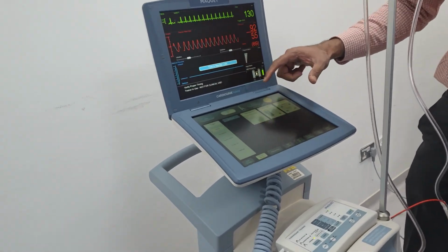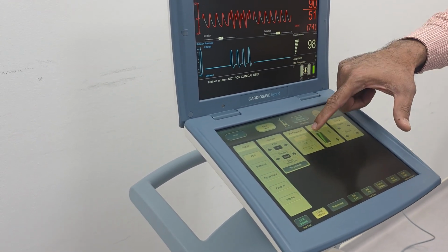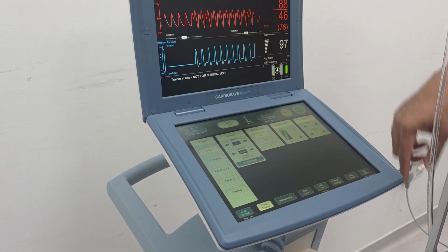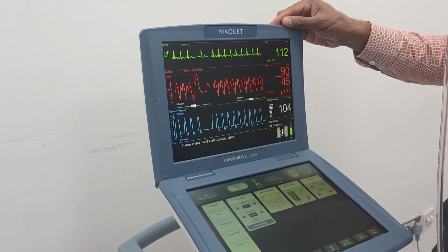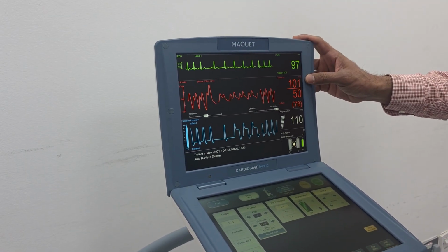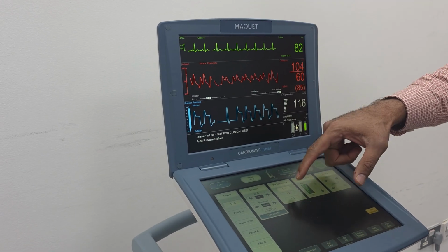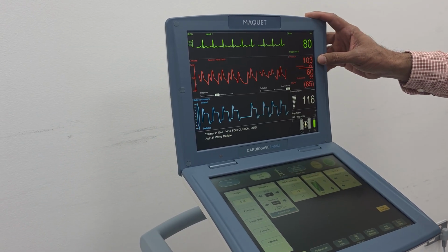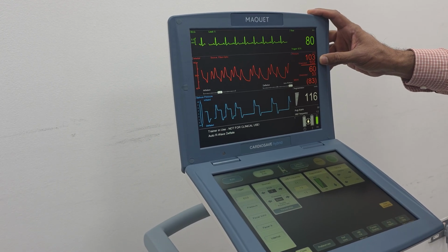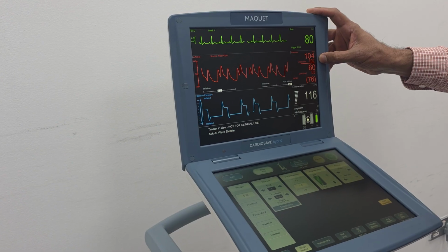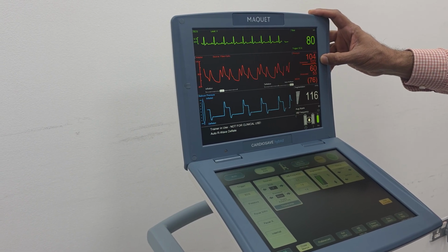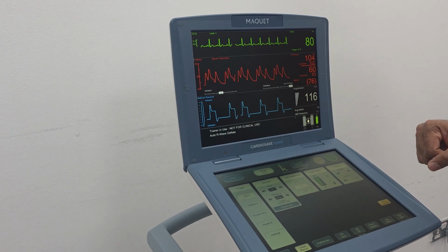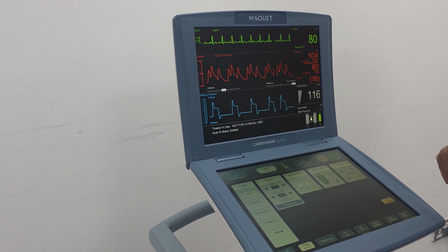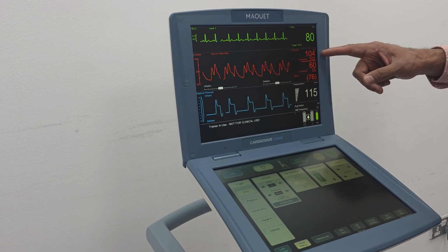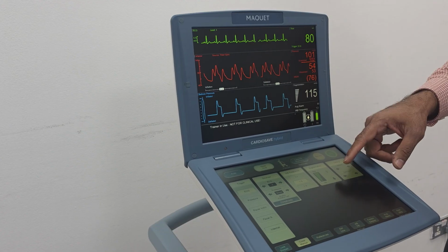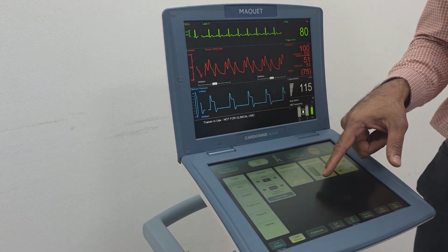Sources, IABP frequency. Okay, we'll start one by one. I will open everything. Frequency, you know, the same way. Now I'll put 1:1 to get a better idea. Now we have systolic, diastolic, mean. But same like CS300, when we go to 1:2, you can see unassisted. So this is the assisted one, this is the unassisted one. Okay, so we have the values. Assisted should normally be less than unassisted. And here we can go to 1:3, but we are not recommending 1:3 more than 30 minutes, again for thrombus formation.